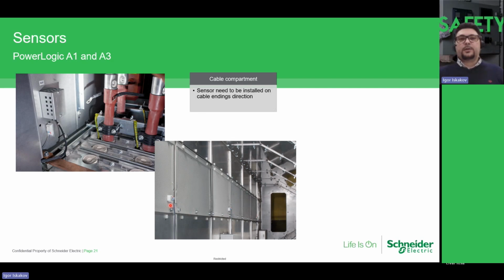And here is an example of the bus bar sensors installation. Behind these plates is the bus bar. If it's a bus bar like one tube, and there are no visible separated walls between the compartments of one cubicle and the second cubicle, we suggest and recommend using sensors installed in every second cubicle, because the visibility will be enough to cover the bus bar compartment. So this is also a way to save money during engineering. Of course, if each cubicle has visible blocking walls, in this case we recommend installing one sensor in the cable compartment of each cubicle.